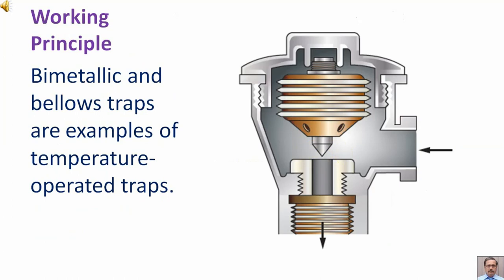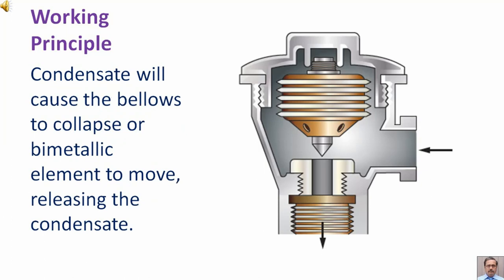Bi-metallic and bellows traps are examples of temperature operated traps. Condensate will cause the bellows to collapse or bi-metallic element to move, releasing the condensate.